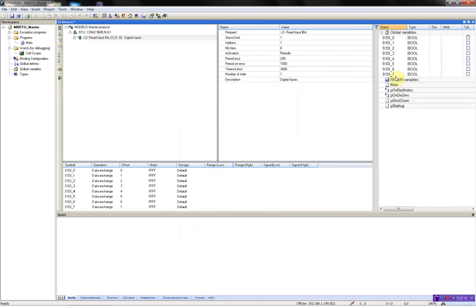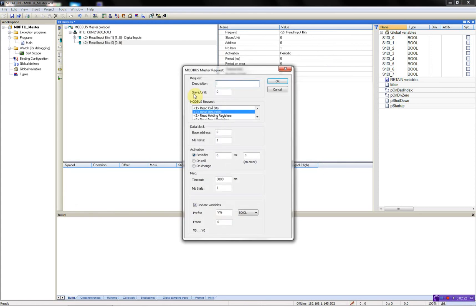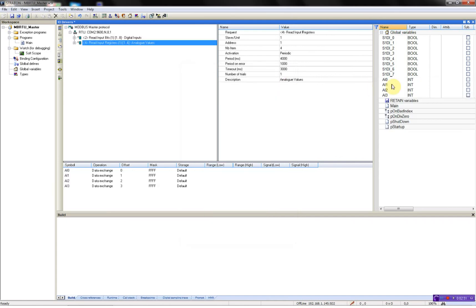As you will see here, we have all our digital inputs. Then I'll add an analog. Analog values, slave one. Read input registers. Four items, request this every 4000 milliseconds, and on error, one second. And I'll add the variables: analog input zero. And again, the variables are automatically created.